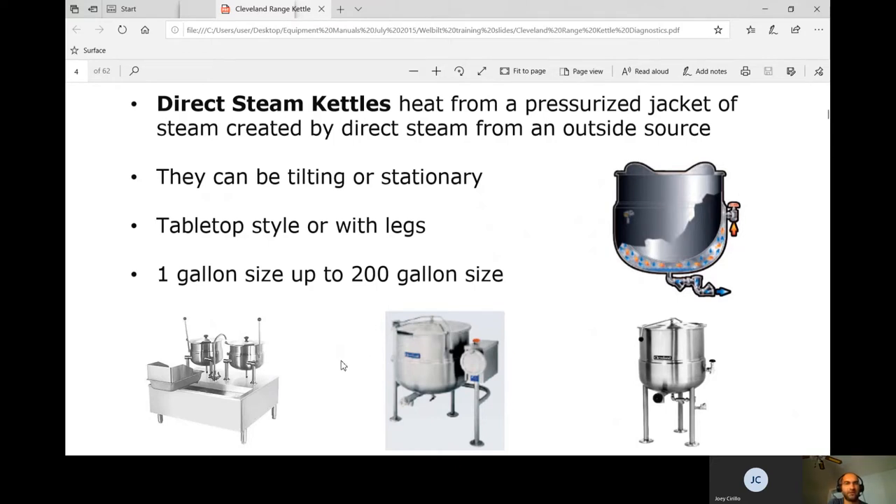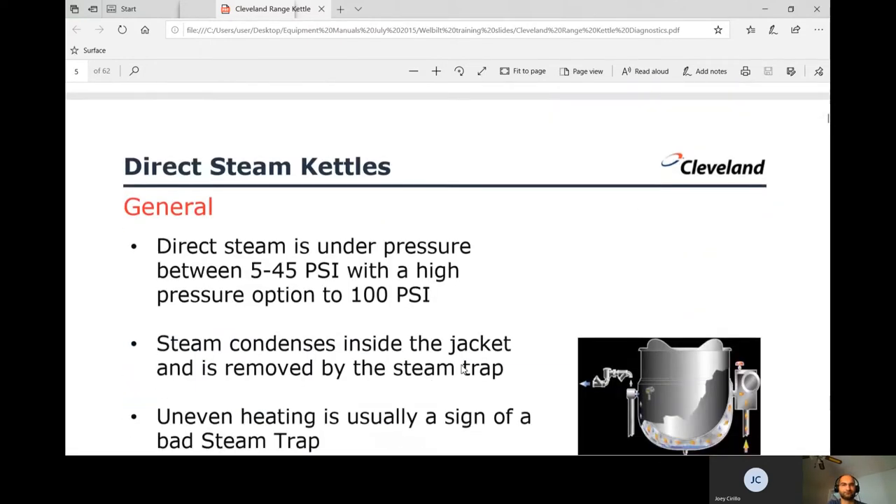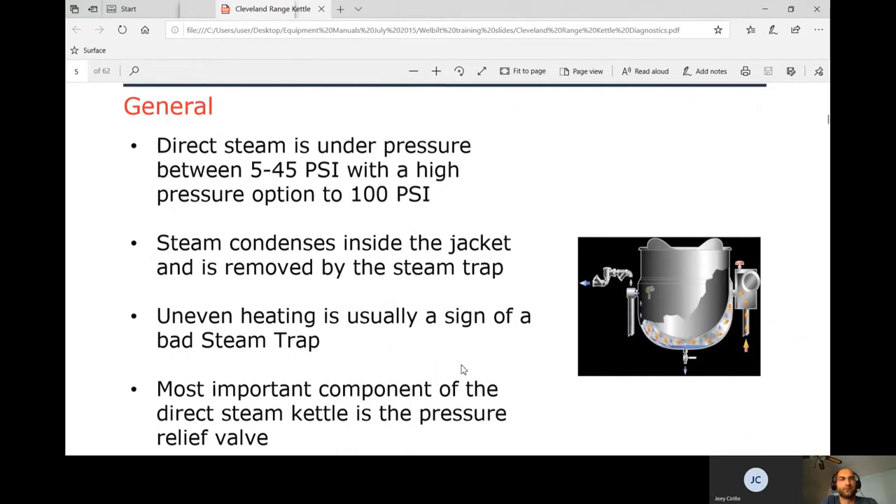They come in tabletop style or with legs, ranging from one gallon up to 200 gallon. The model number — like 1240 — designates the gallon size. Direct steam operates under pressure between 5 and 45 psi, with a high pressure option up to 100 psi.